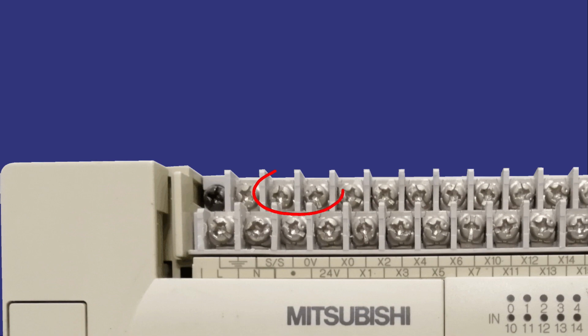And these two terminals, S/S terminal and 0 volts terminal, should be connected together. The S/S terminal is used to configure the unit's inputs for sinking or sourcing signals all at once. This terminal is 24 volts, and we need it to be our potential voltage across the input devices.